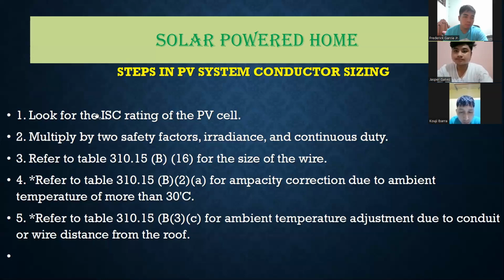Now we multiply the ISC by the irradiance and continuous duty. Then we refer to the table I showed earlier for the appropriate size of wire, which we guesstimate. Then we multiply that for ampacity correction if the ambient temperature is more than 30 degrees Celsius. Then we also adjust for the ambient temperature adjustment due to conduit or wire distance from the roof.